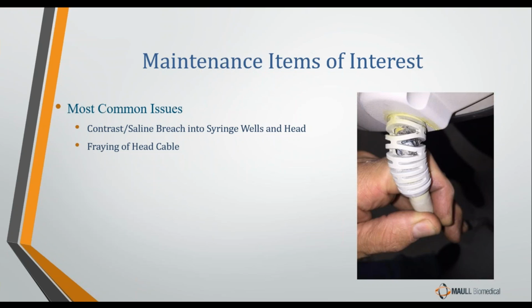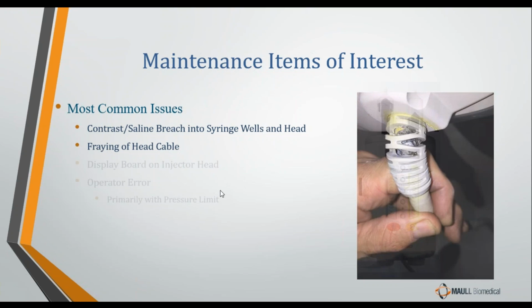Replacing a head cable, you don't need special training to replace a head cable. Any general biomed, any imaging biomed could do it. It's just sometimes a little time consuming because when you take the covers off, there's a lot of strain reliefs, there's a lot of tie straps you've got to cut. So it's not difficult. It can take anywhere from 15 to 30 minutes depending on the model of the head cable that you're swapping out.